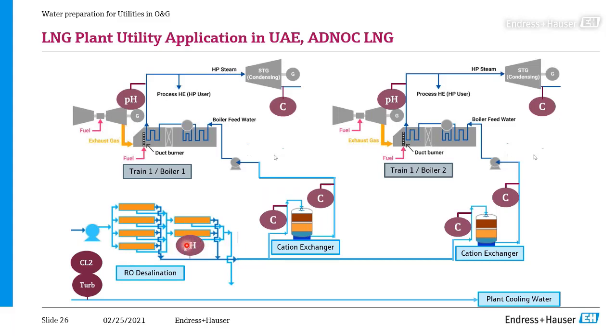At this point we measure the pH, then it goes to the cation exchanger. So you measure conductivity before the cation exchanger and after it, to make sure we don't have any impurities left, and then the boiler feed water with good quality gets into the boiler.